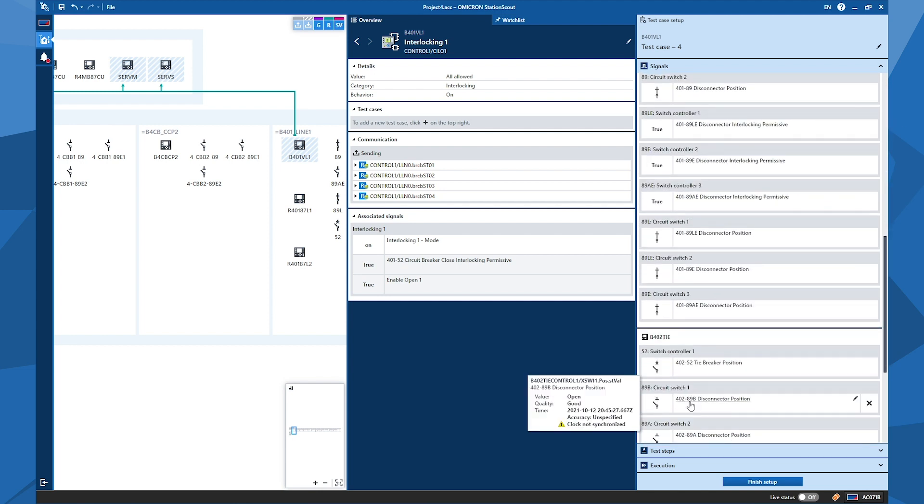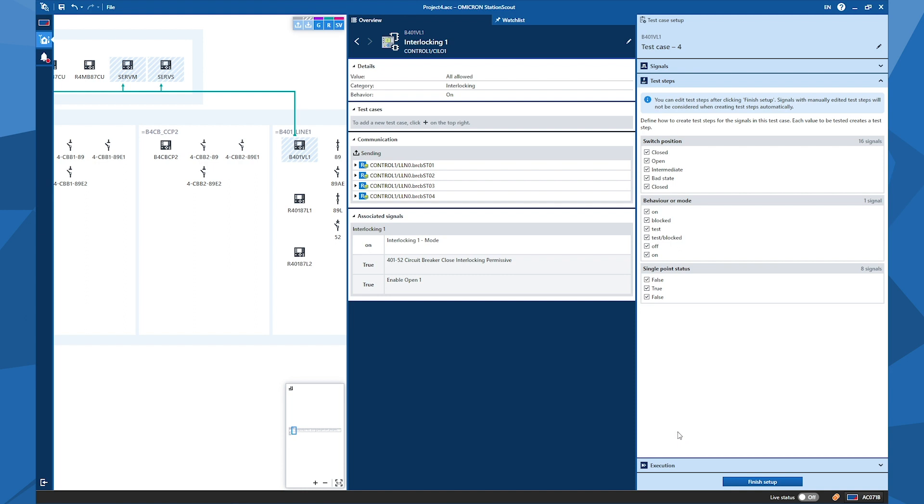So now I can go to the next step. Next step is called test steps. So here you see Station Scout is offering predefined test steps to be generated for me. You see that all different statuses for different data types are offered. For instance, for enumerated values, we have all the statuses. These are defined. For single point signals, we have a false-true-false cycle. For positions, we offer starting from closed and ending up with closed again. Please notice that we always finalize the last step as the same with the first step to go back to the initial state. This will help you later on for ease of notice which equipment is tested and which is not yet tested. You can deselect some of the statuses that you don't want to test as per your requirement.